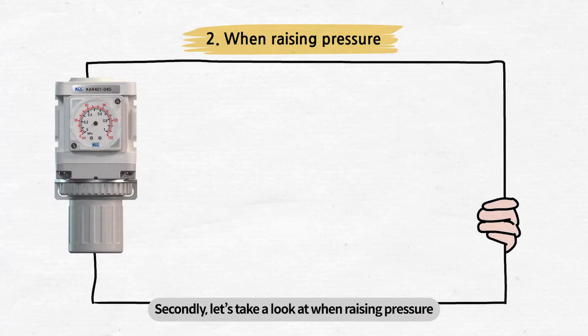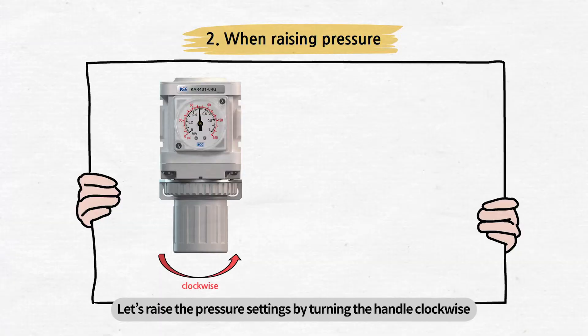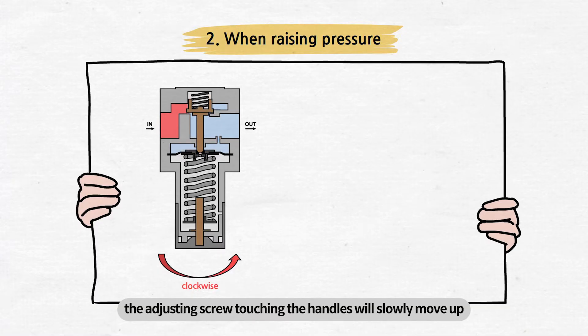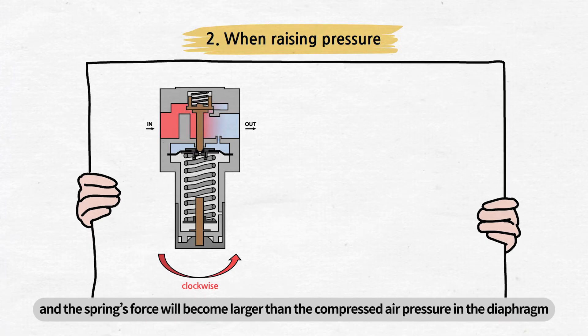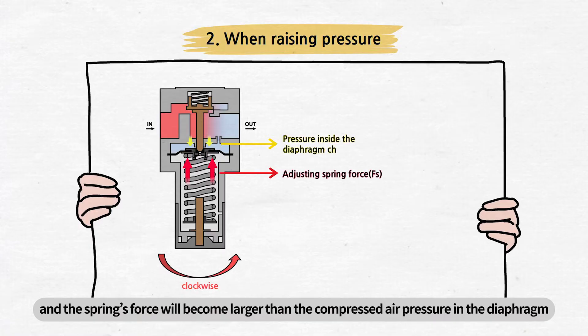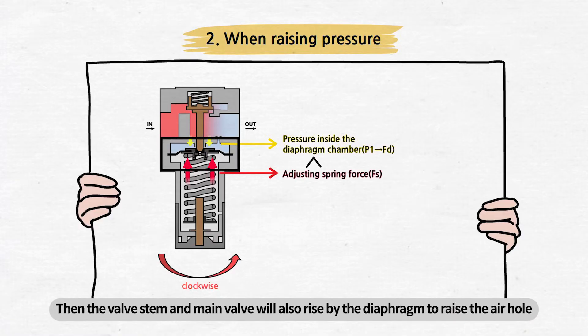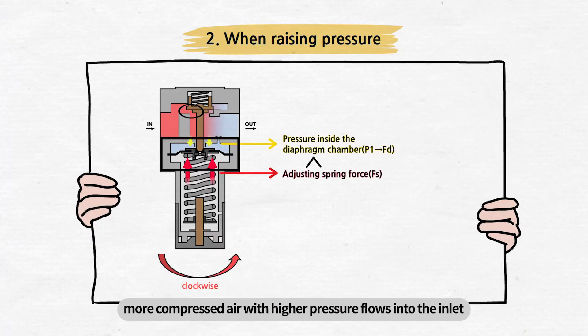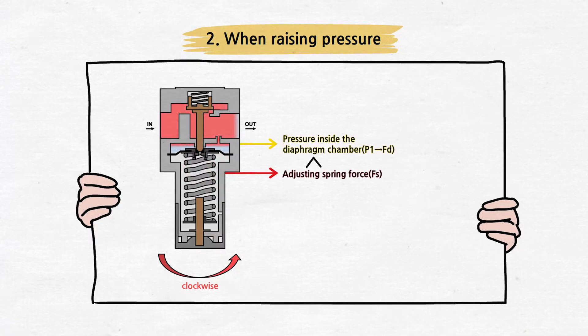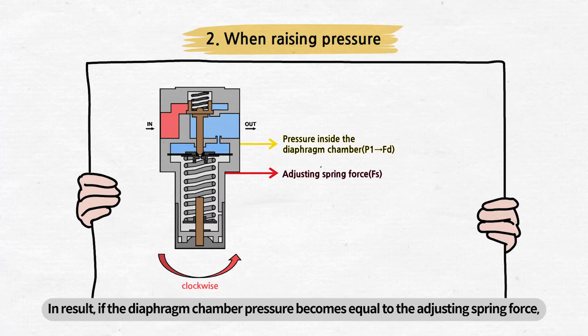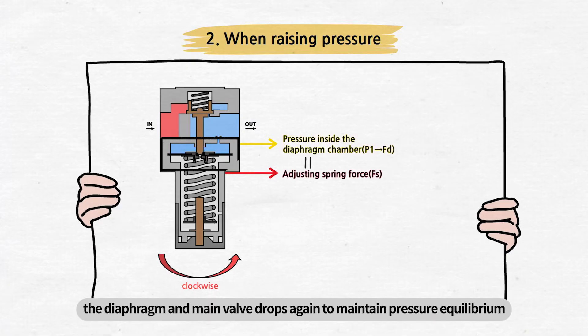Let's take a look at when raising pressure. Let's raise the pressure settings by turning the handle clockwise. By turning the handle clockwise, the adjusting screw touching the handle will slowly move up. Then, the adjusting spring will compress and the spring's force will become larger than the compressed air pressure in the diaphragm chamber to raise the diaphragm. Then, the valve stem and main valve will also rise by the diaphragm to open the air hole. As the air hole becomes more open, more compressed air with higher pressure flows into the inlet. Then, the pressure at the outlet and diaphragm chamber gradually rises again. If the diaphragm chamber pressure becomes equal to the adjusting spring force, the diaphragm and main valve drop again to maintain pressure equilibrium.